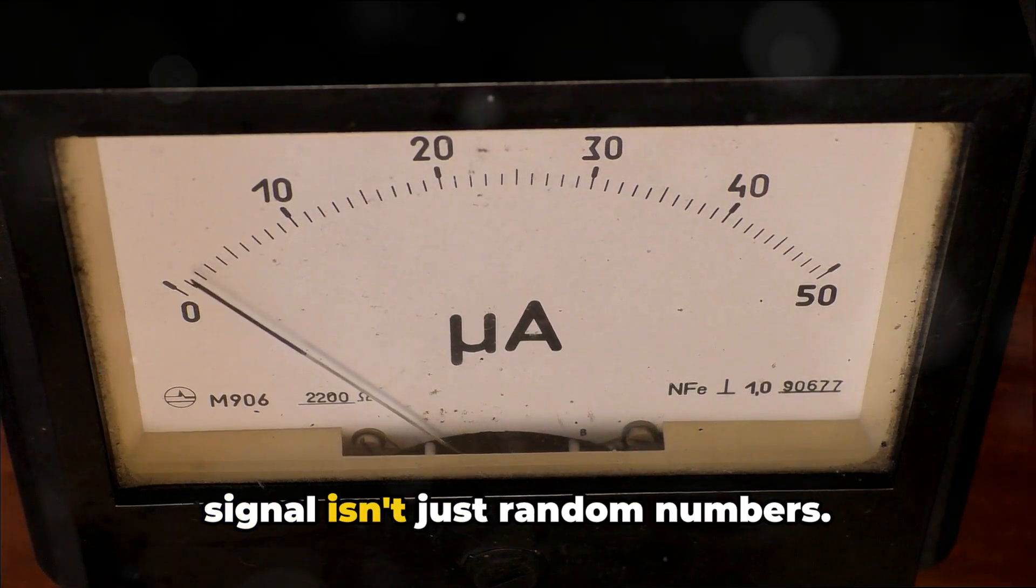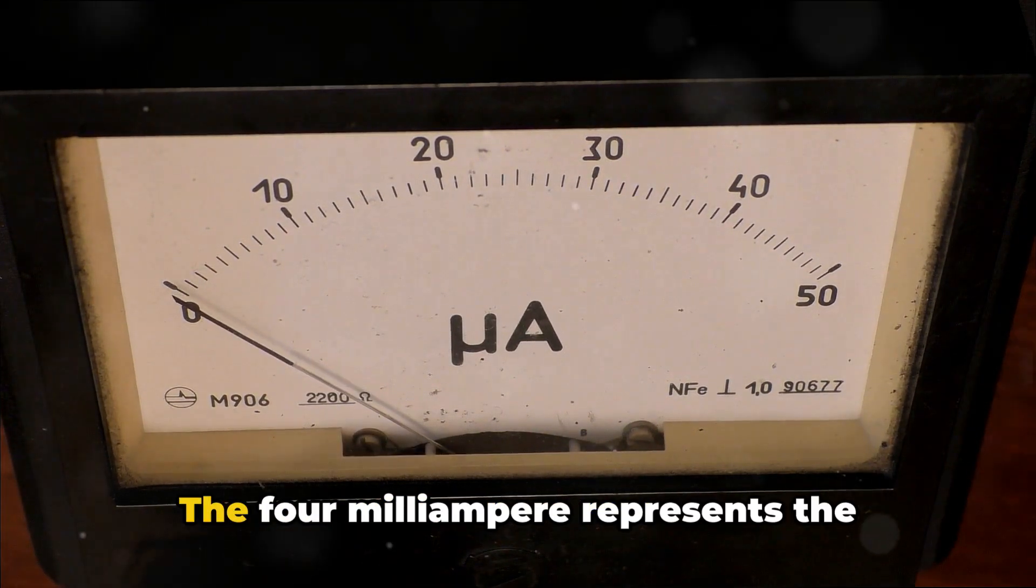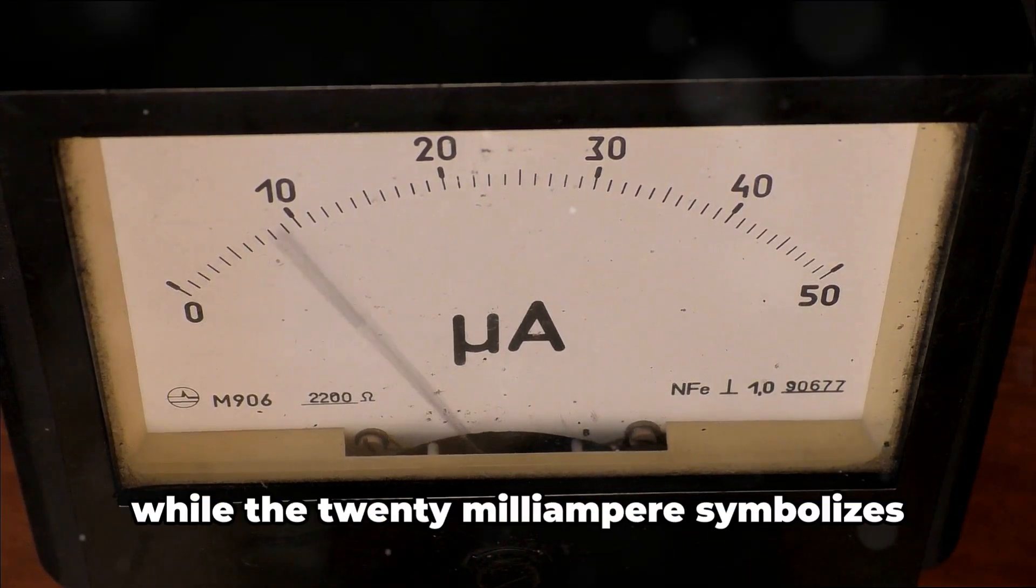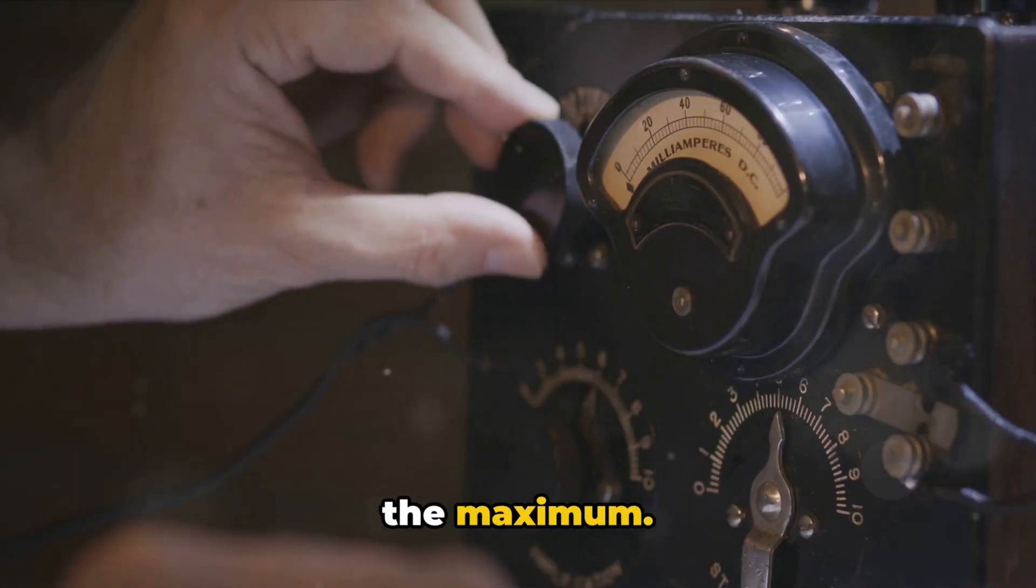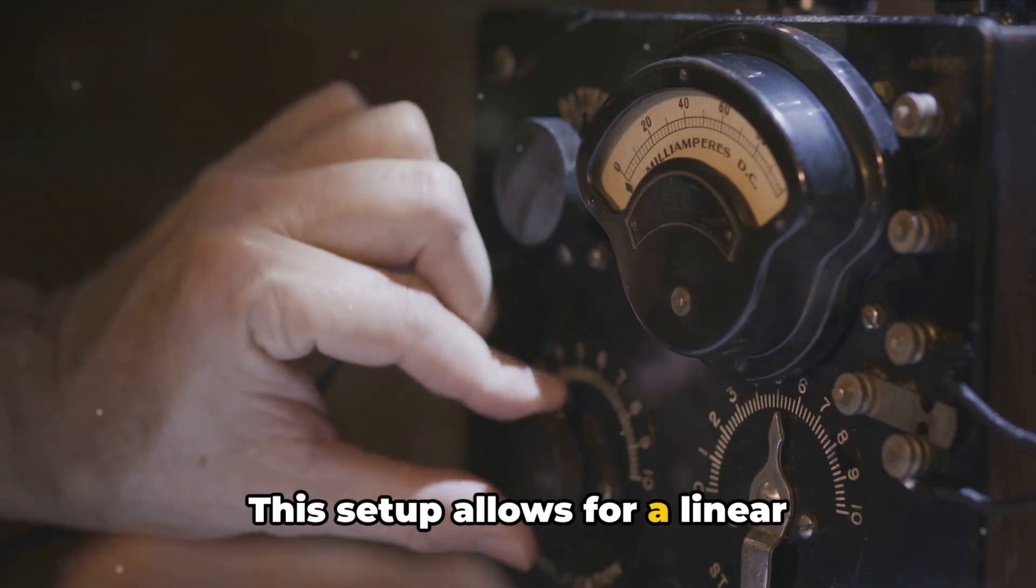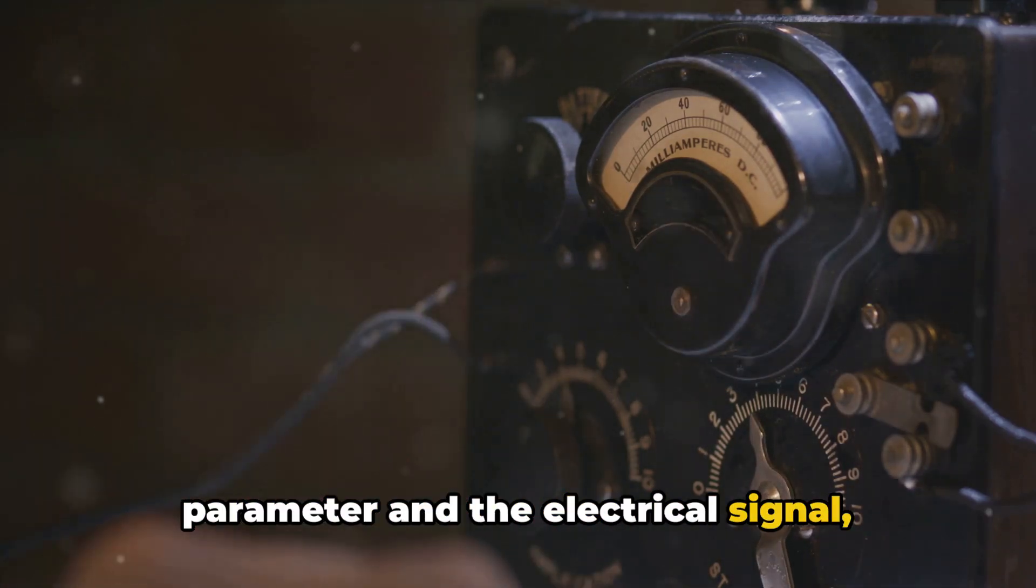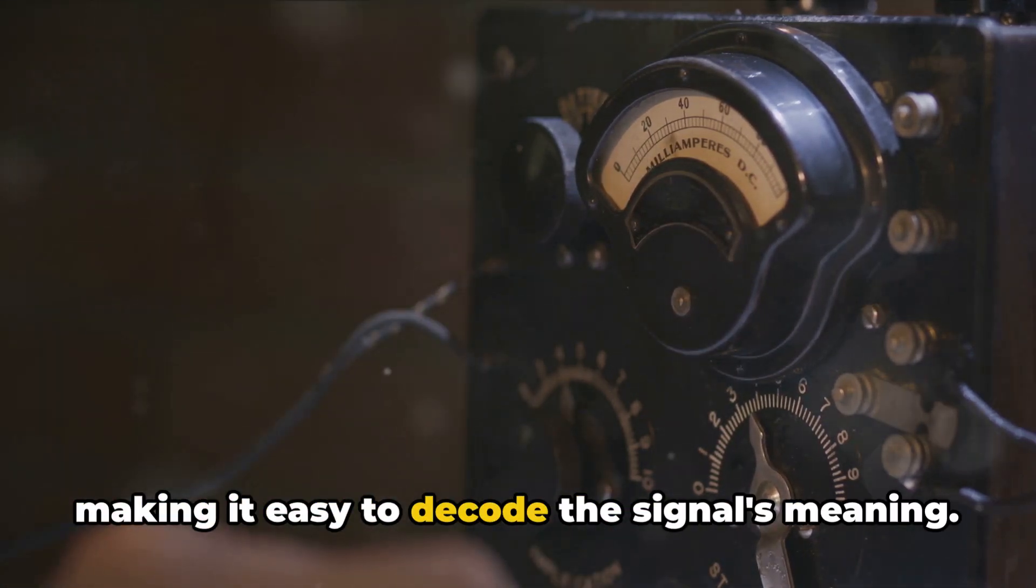The 4-20mA signal isn't just random numbers. The 4 milliampere represents the minimum value of the measured parameter, while the 20 milliampere symbolizes the maximum. This setup allows for a linear relationship between the measured parameter and the electrical signal, making it easy to decode the signal's meaning.